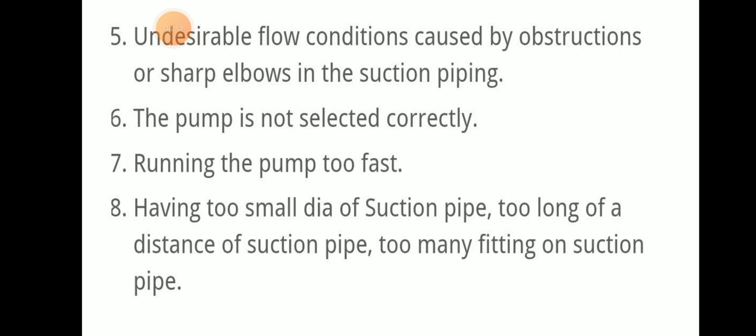Also, the pump not being selected correctly, running the pump too fast, having a small diameter of suction pipe, too long a suction distance, or too many fittings on the suction pipe may also be reasons for cavitation.